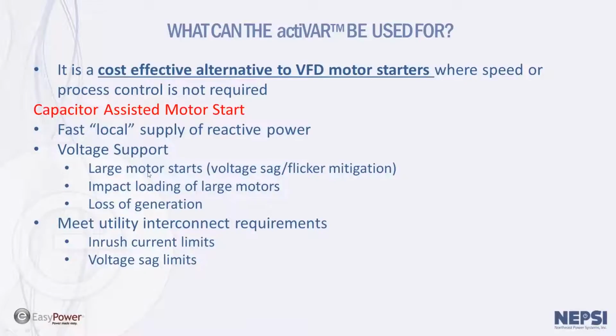It can support voltage for large motor starts and also support voltage for flicker type applications, which include welder and induction furnace type applications. It can also take care of impact loading of large motors. Such applications might include dragline shovels or car crushers. And it can also take care of voltage dips that might take place due to loss of generation within a facility that has local generation. The actiVAR can help a customer meet inrush current limits or voltage sag limits that might be required for a large motor starting.